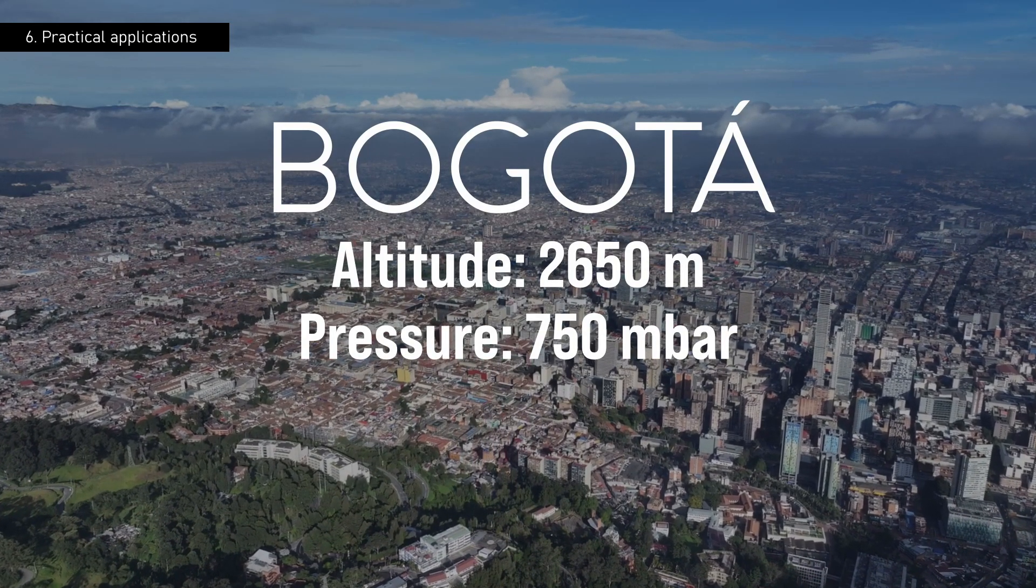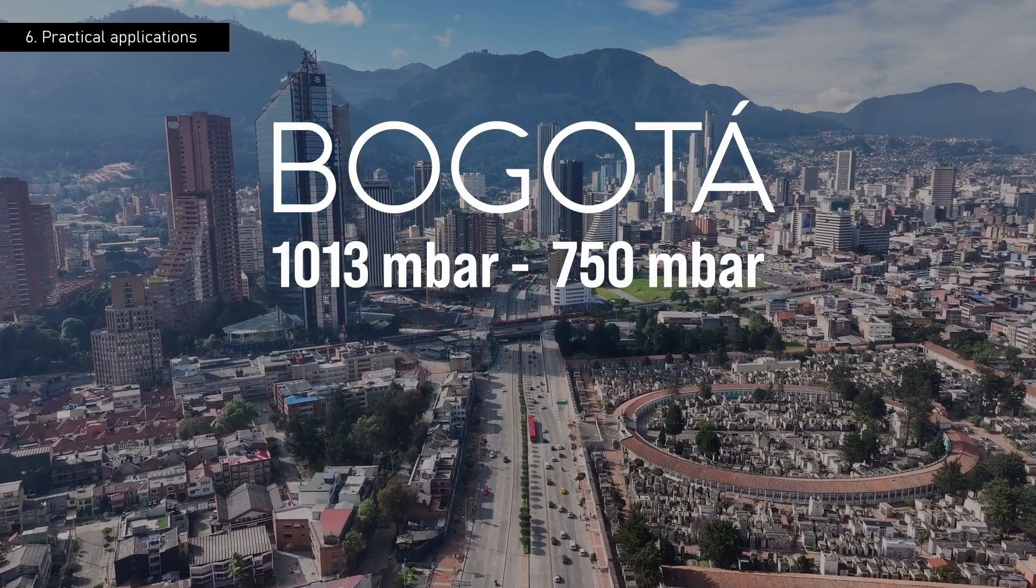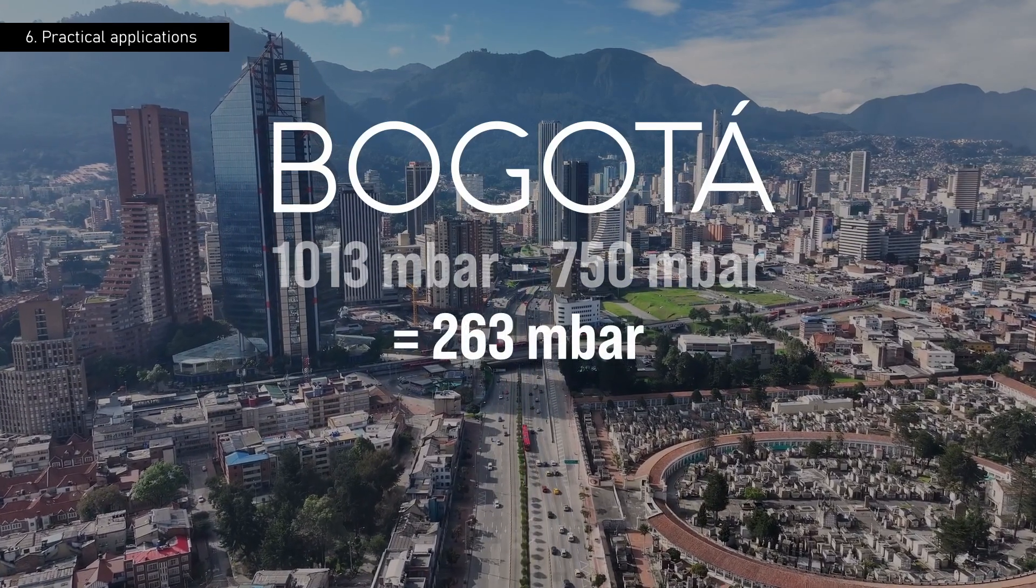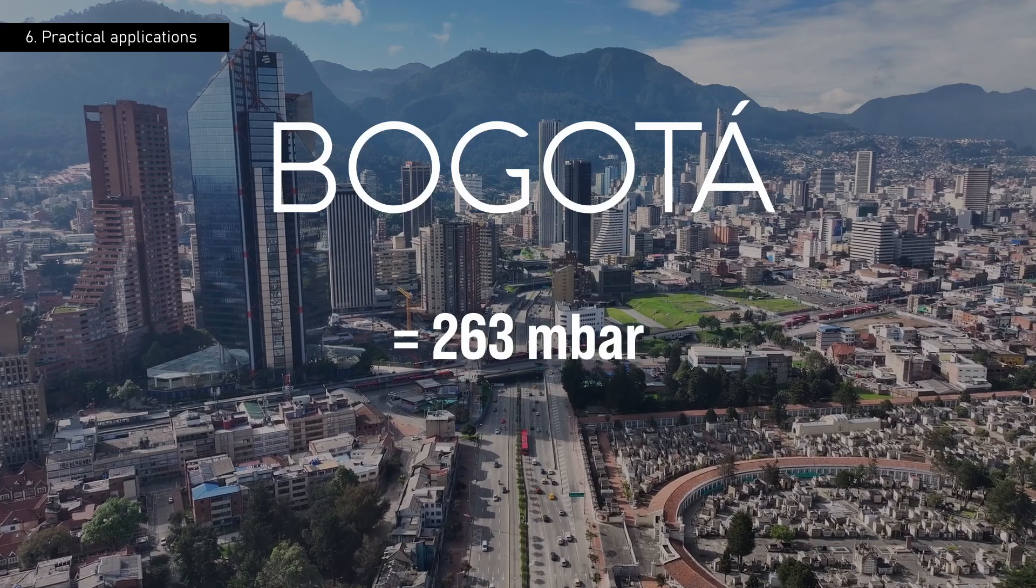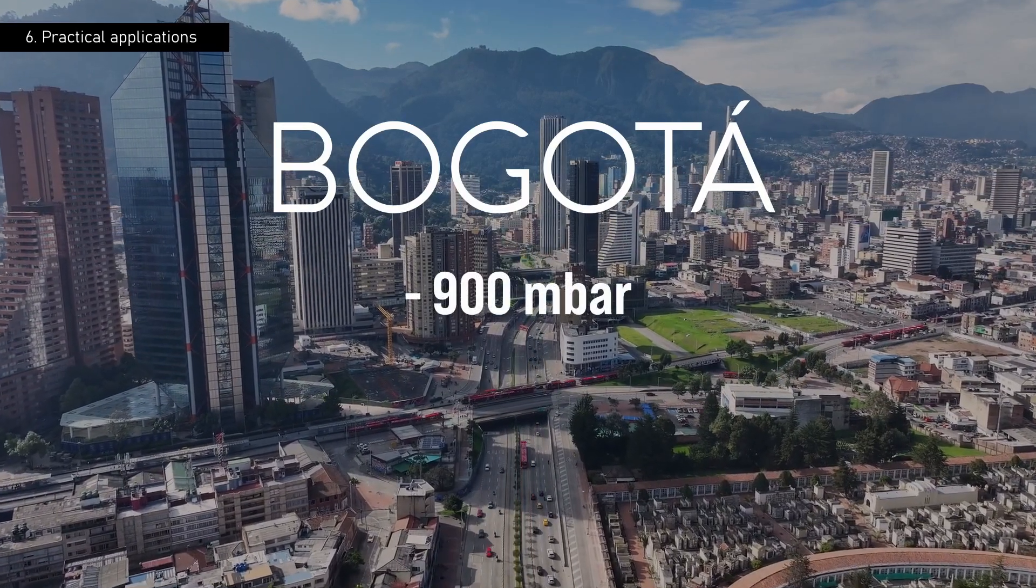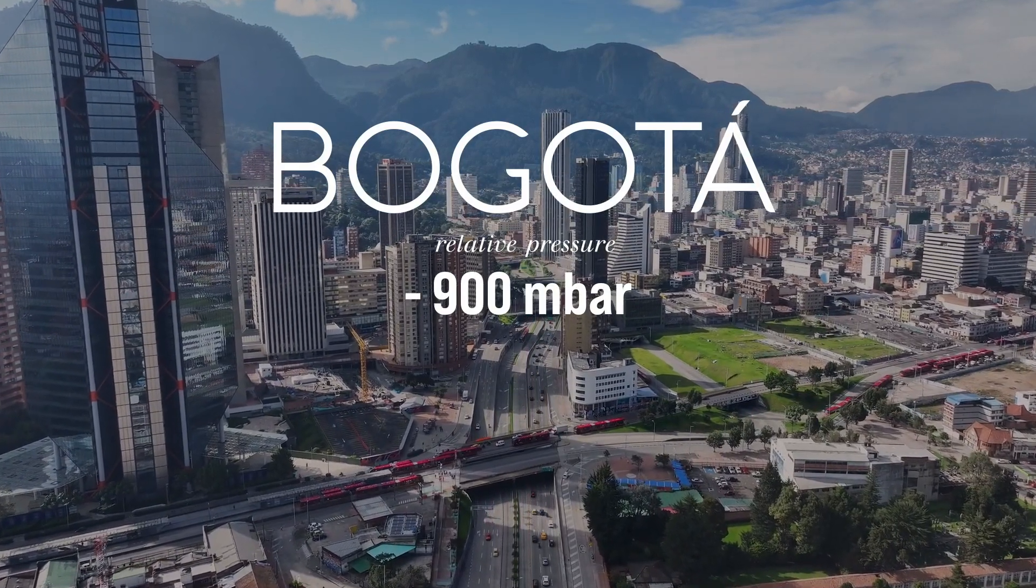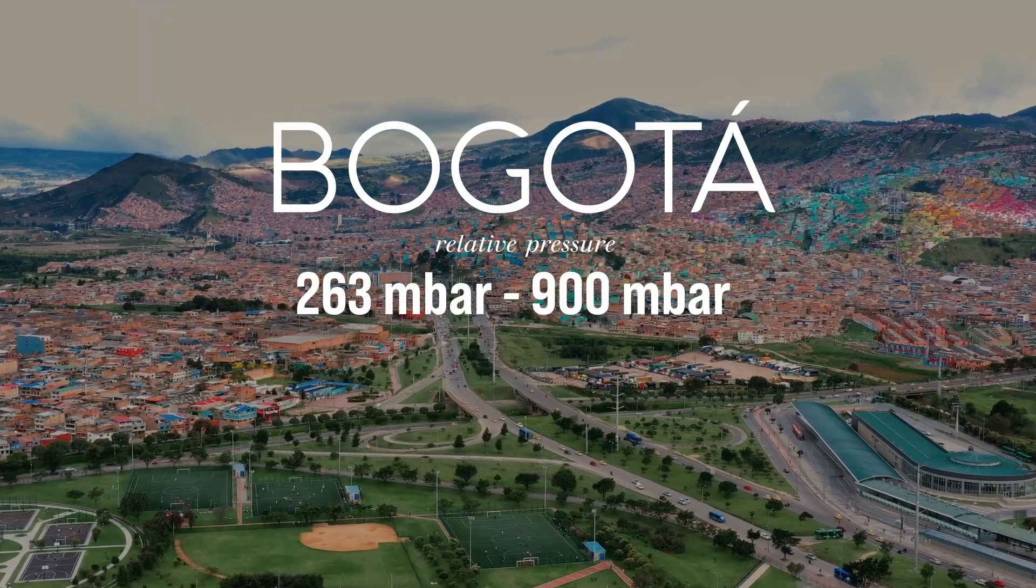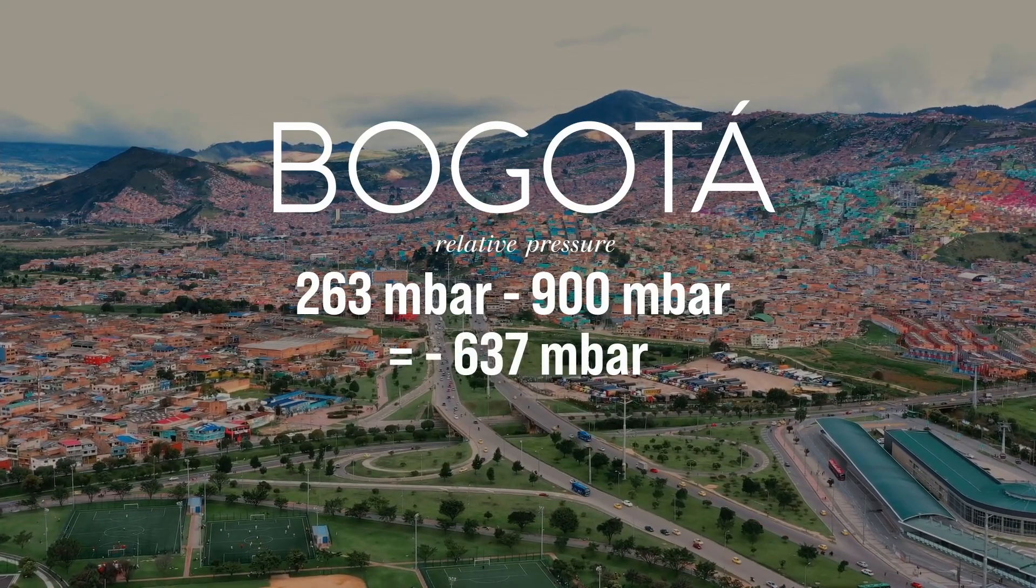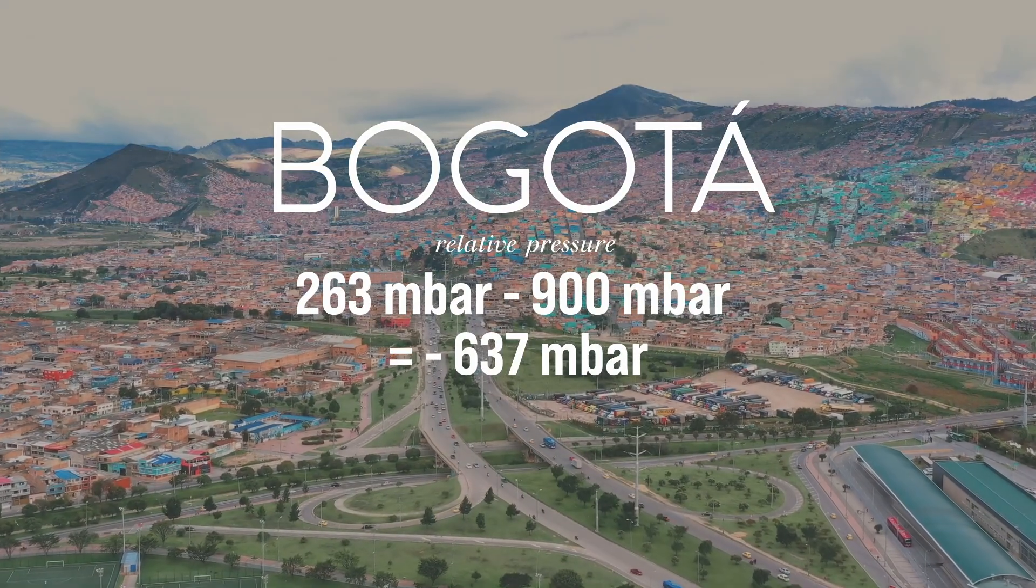First, we must calculate the pressure difference between this city and sea level. 1,013 millibars minus 750 millibars gives us a result of 263 millibars of difference. Let's set this number aside and remember that the vacuum chamber can generate a maximum of minus 900 millibars of relative pressure at sea level. If we subtract the 263 millibars of difference from this number, we get a result of minus 637 millibars. This is the maximum level of vacuum that our pumps can reach, being in the city of Bogota.